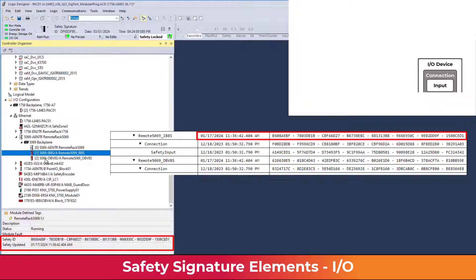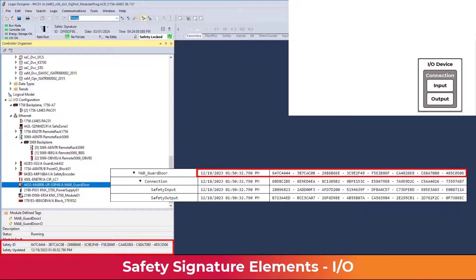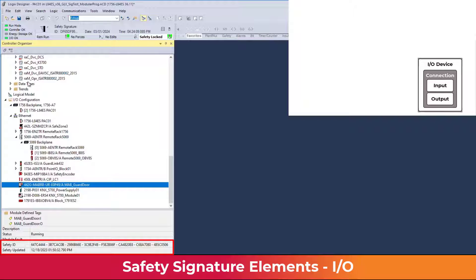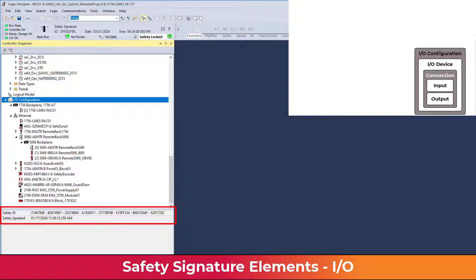A safety output device adds an output signature for output data, creating a total of four signatures per output device. Devices with both safety inputs and outputs have the same four-signature structure. All of the safety modules in the IO configuration combine to create an overall safety IO configuration signature.